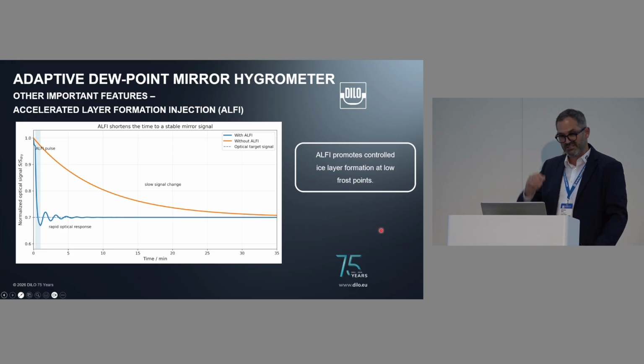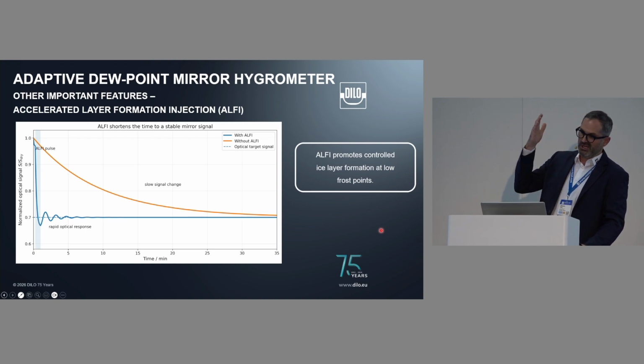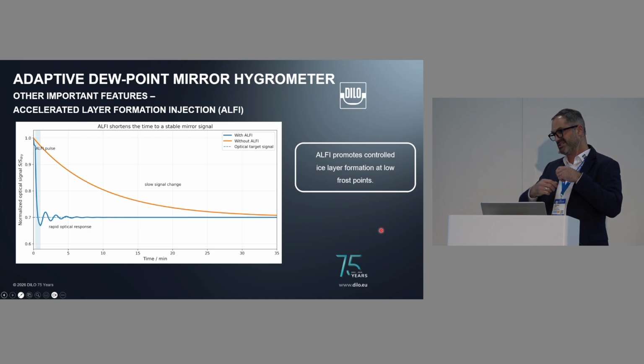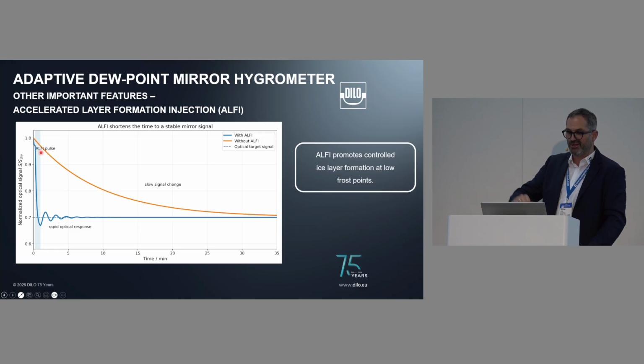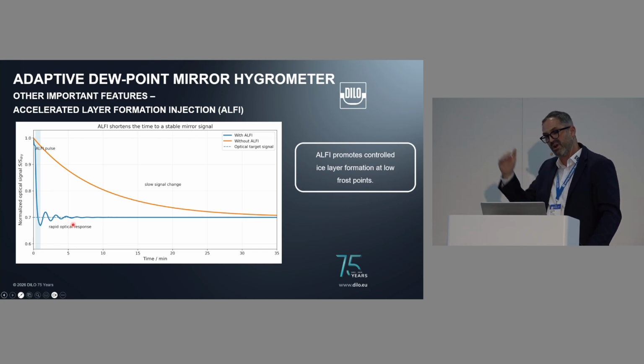Another important thing is that, for example, if you measure at very, very low humidities, we are talking about some hundreds of water molecules in 1 million gas molecules, and it would really take a very long time until you have a very stable value. But in this case, we don't want to wait so long. So what we do is basically we inject an impulse of high concentration of water vapor, and this increases basically the ice formation, and then we have the ice layer on the mirror, and then it stabilizes around that value.